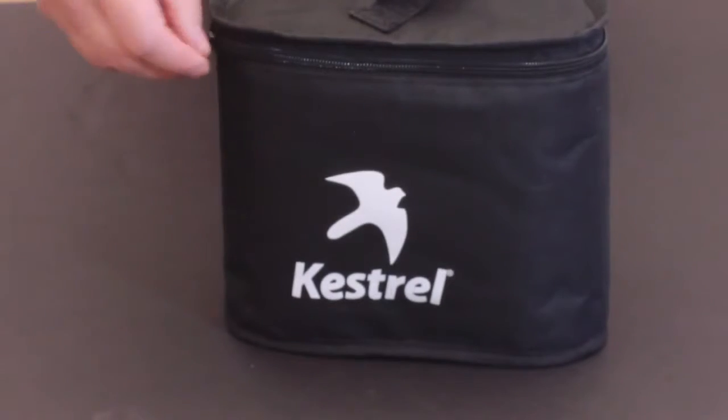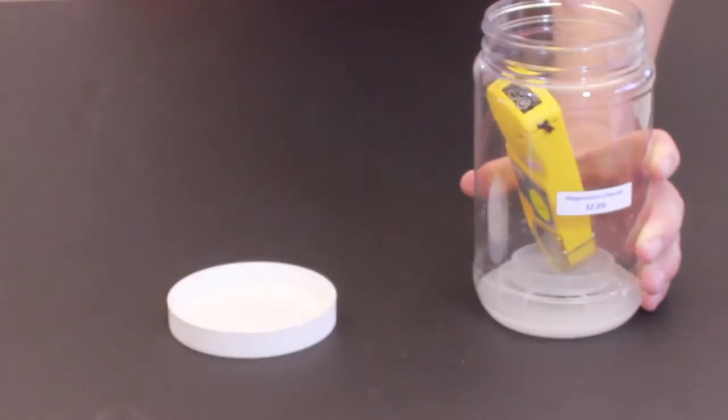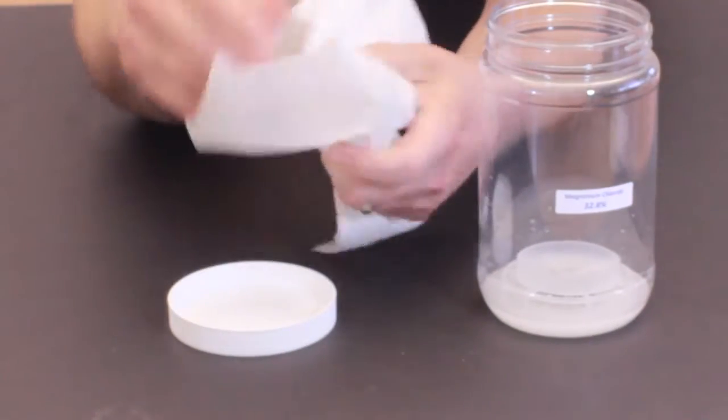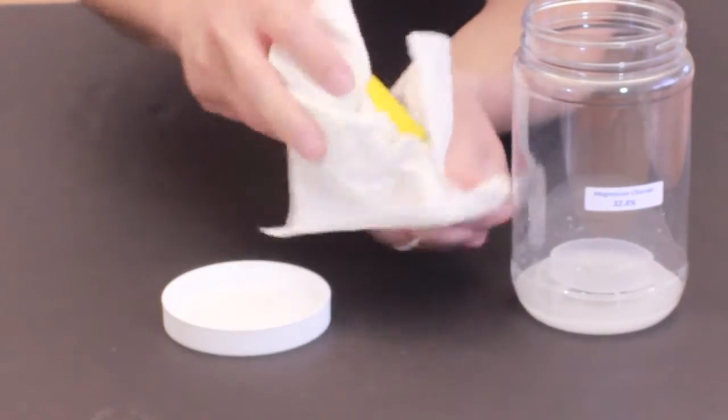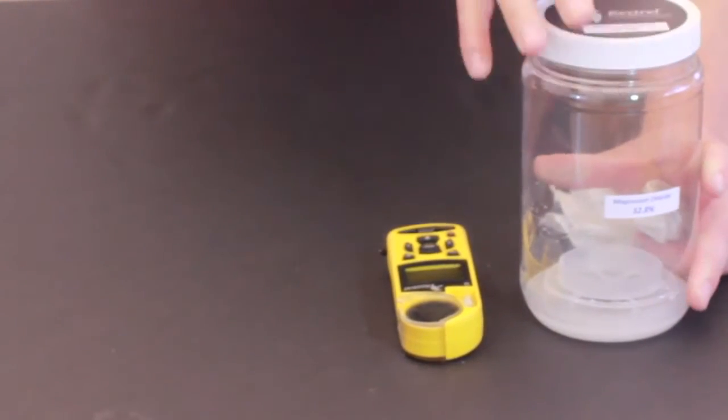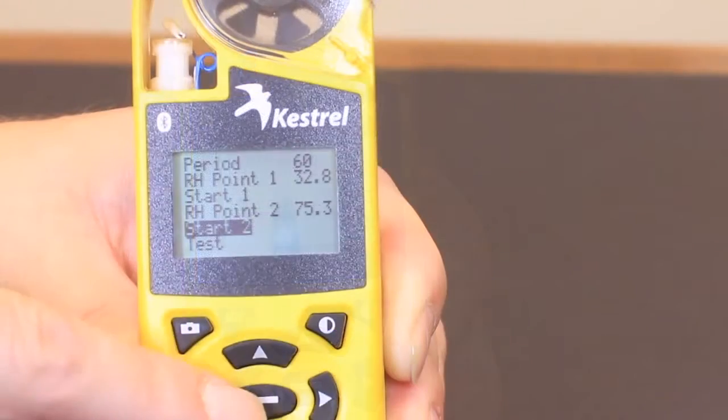So an hour has passed. We'll open up our calibration kit, pull out the magnesium chloride chamber, open it up, and we're going to make sure we wipe off any excess salts, including the lanyard, because we do not want these salts to mix with the next container. Once we're done wiping that off, we'll close up the container, and we'll pull out the sodium chloride container. We just pulled the 4500 from the first calibration chamber, and now we're ready to proceed for the second calibration. We'll go to start two. We'll hit the center button.